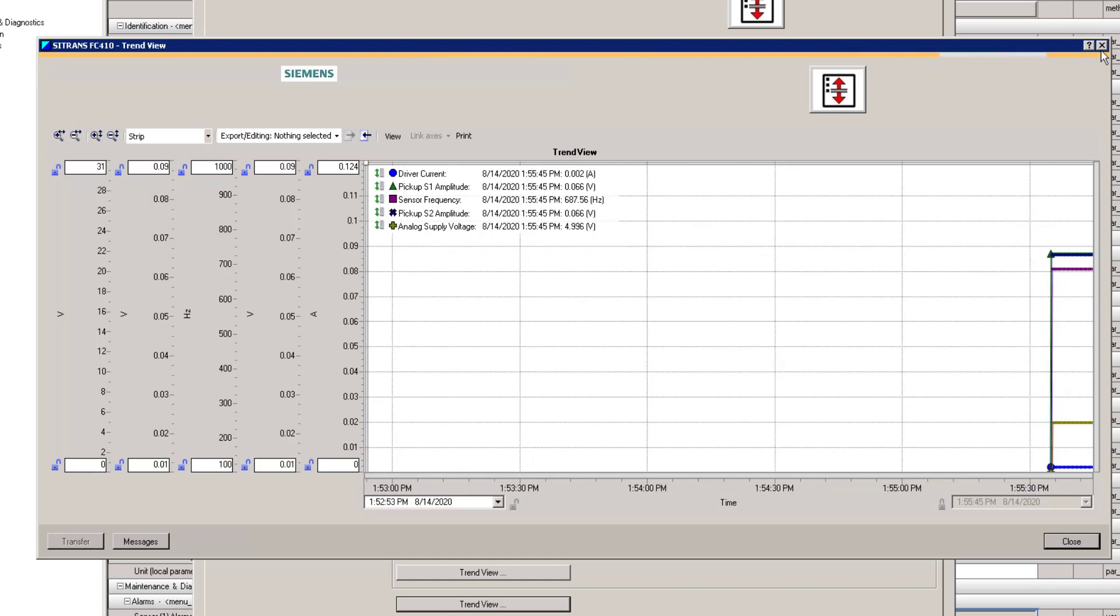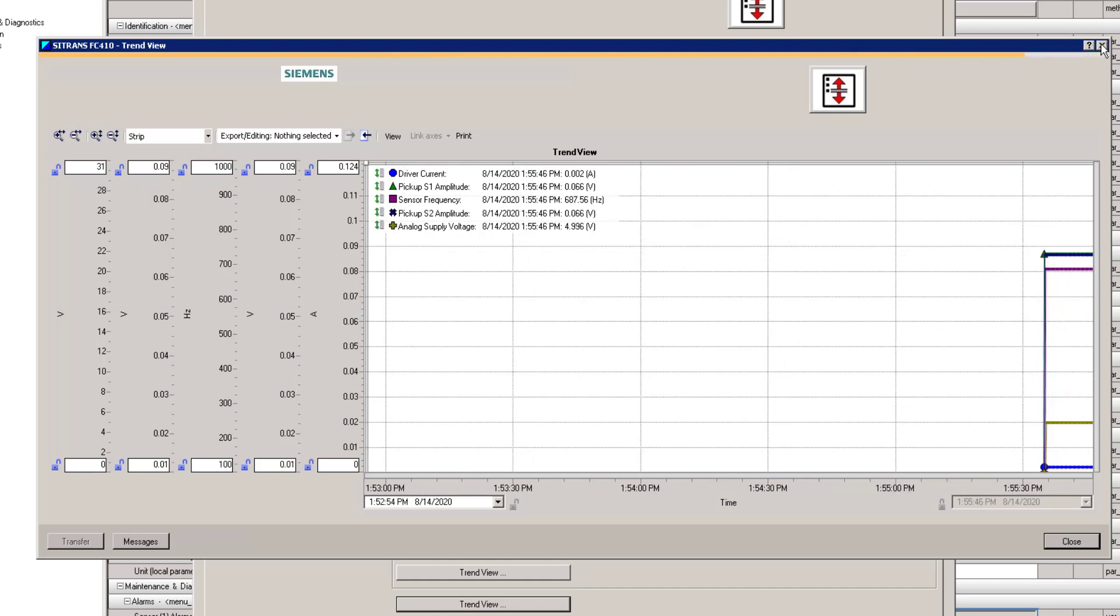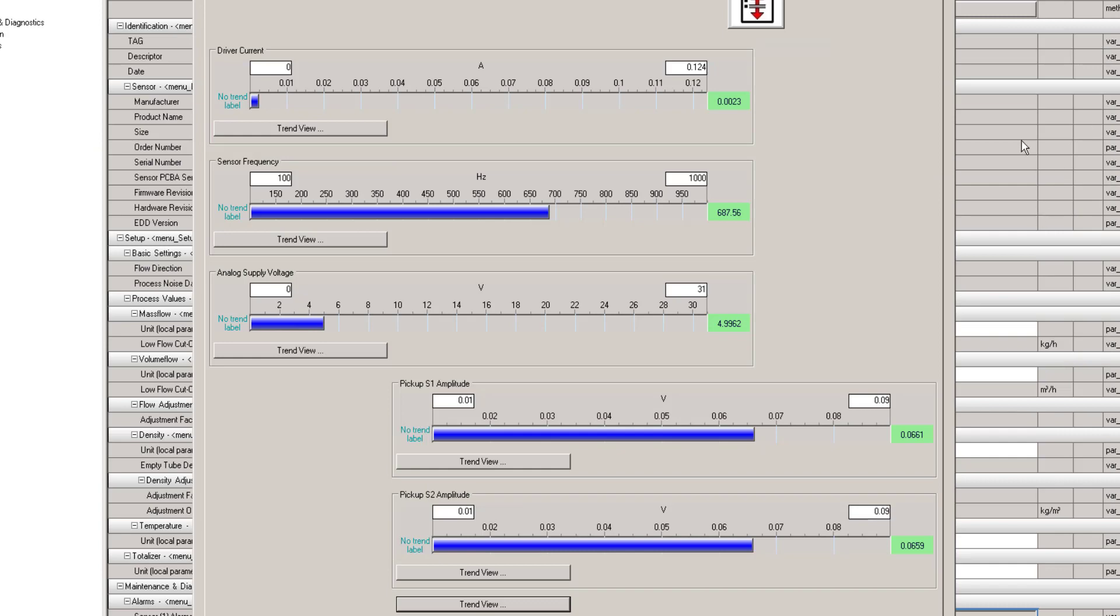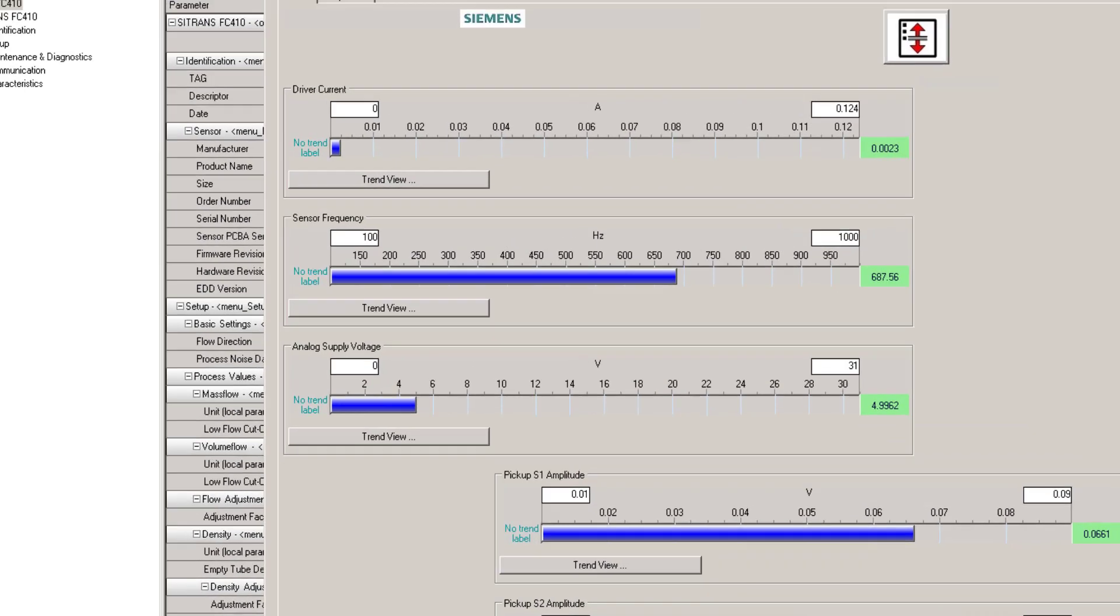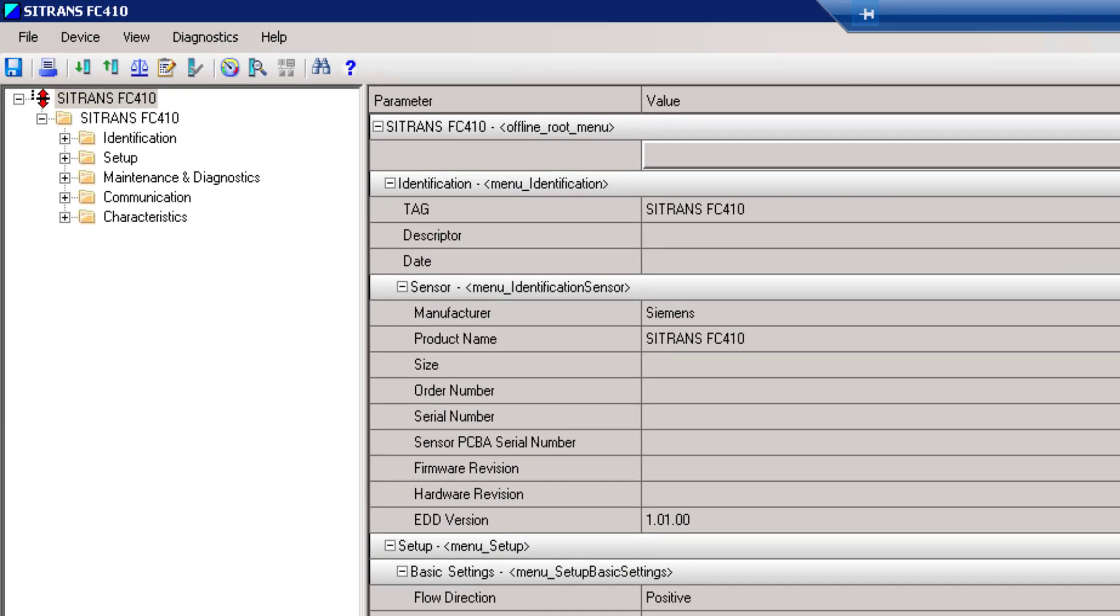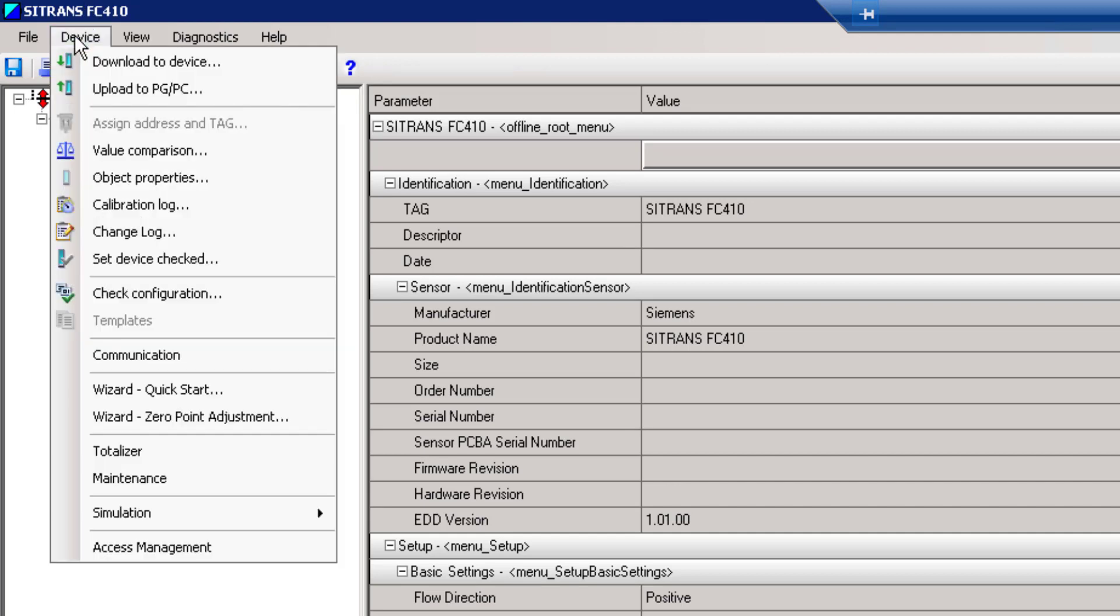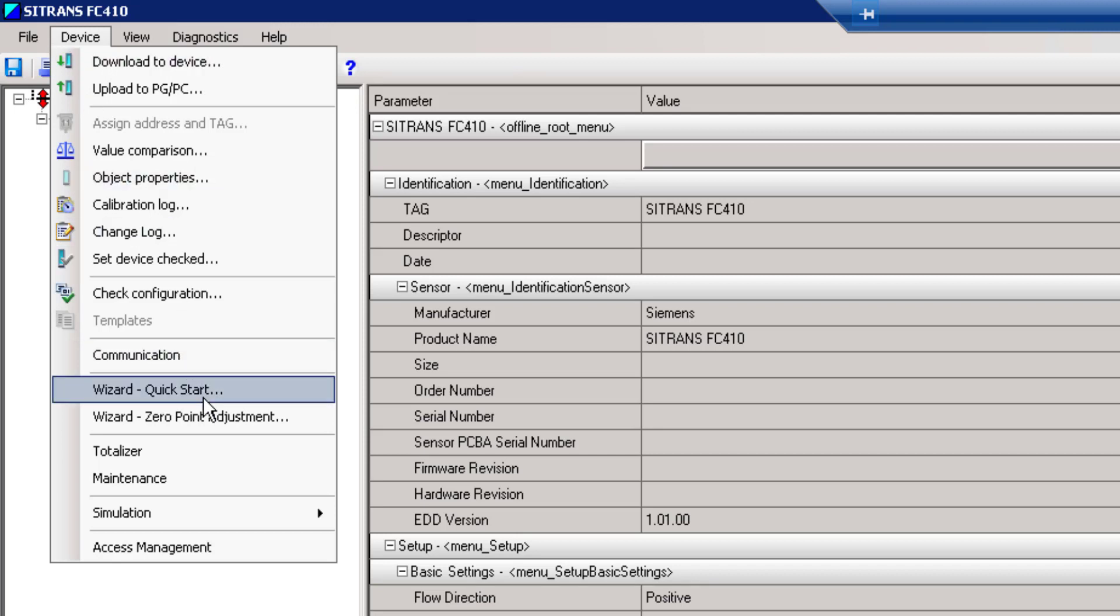But what we need to do, this is a nice simple project. There's only one Coriolis meter. But as I alluded to earlier on, they all come out with the address set as one. So if you put all six on, if you had six of them onto the network in one go, you wouldn't know which one it would be reading. So you've got to connect one at a time. Then you come to this menu, Device. We've already got it set for address one. Then under communication, you'll have some options. But the first thing you need to do is to log in.